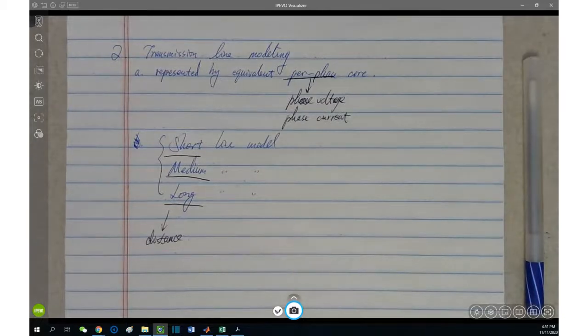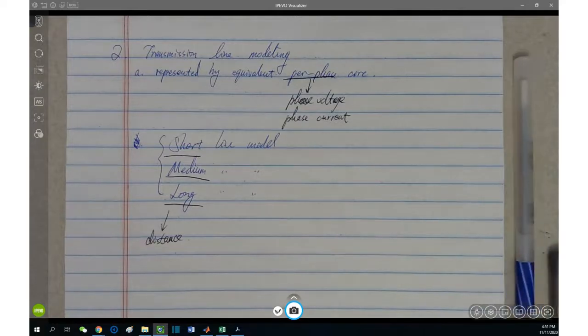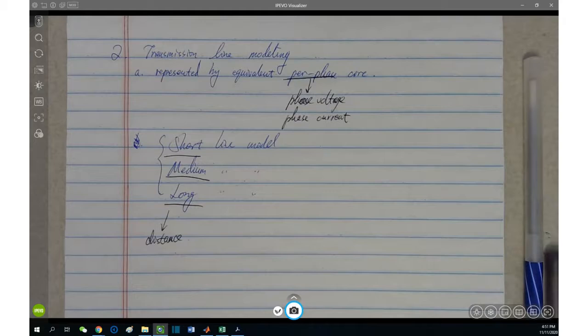It absolutely matters. If you have some motor drive experience, you know your supply line, a three-phase line, the length of it absolutely matters. I don't know if anyone has related experience. You can't make it very long. If you make it very long, you're going to lose a lot of voltage. It's terrible, so this phenomenon is very significant. You have to compensate the reactive power, otherwise you lose a lot of voltage.